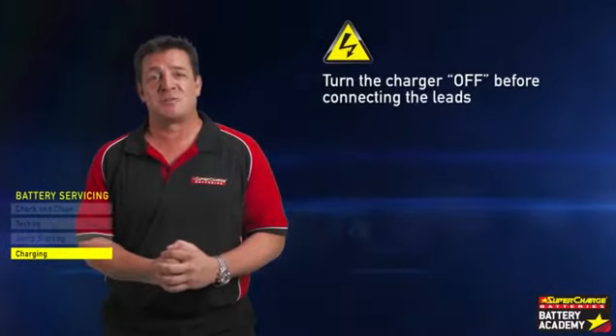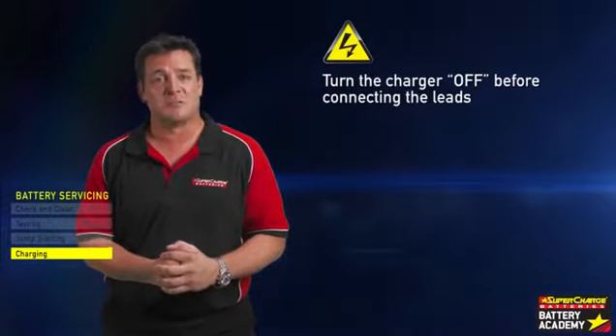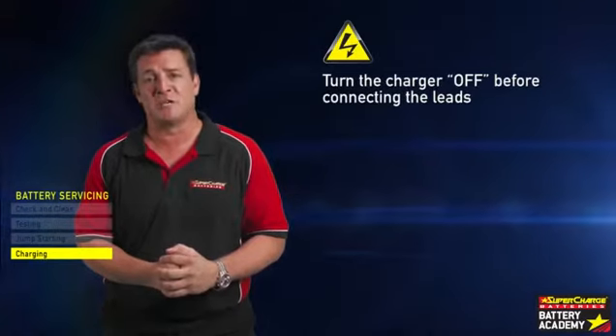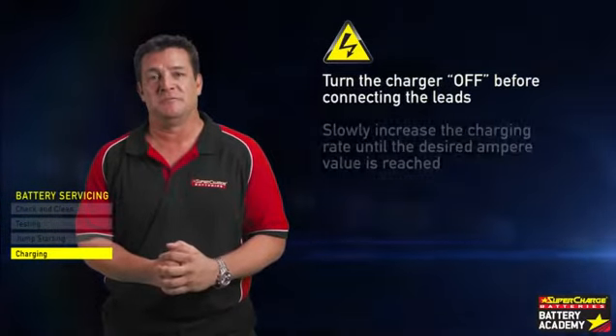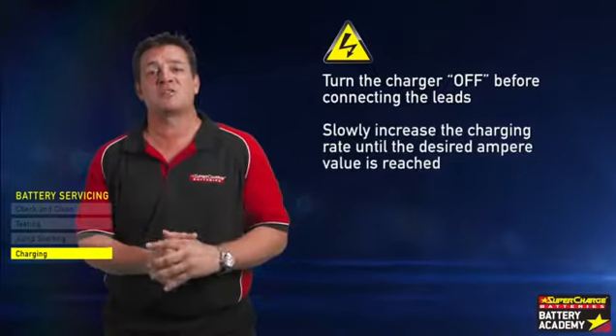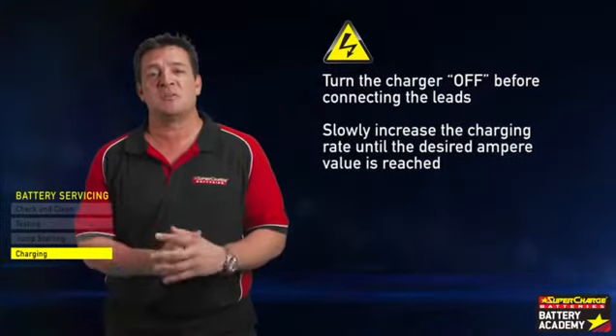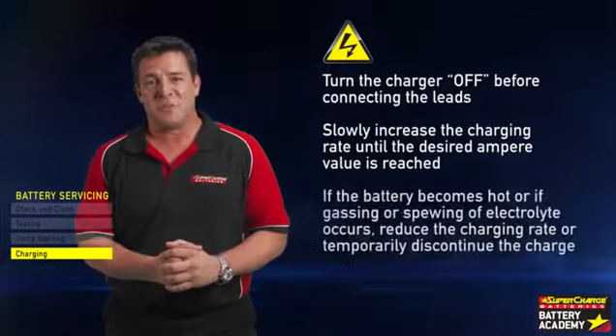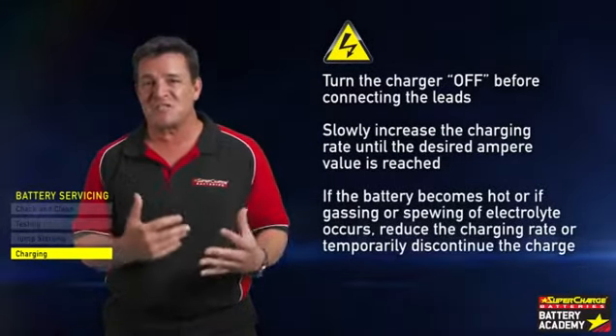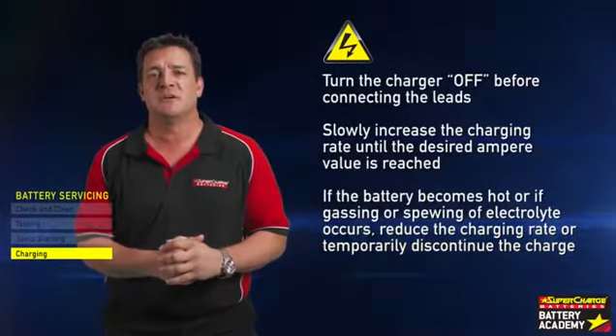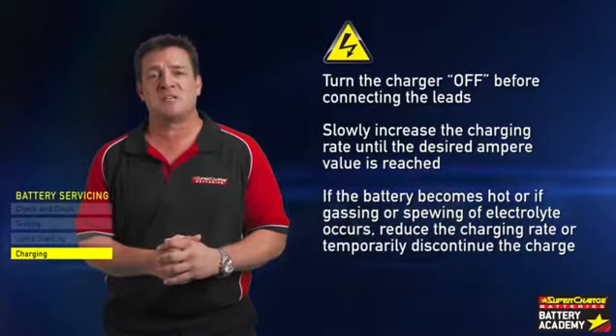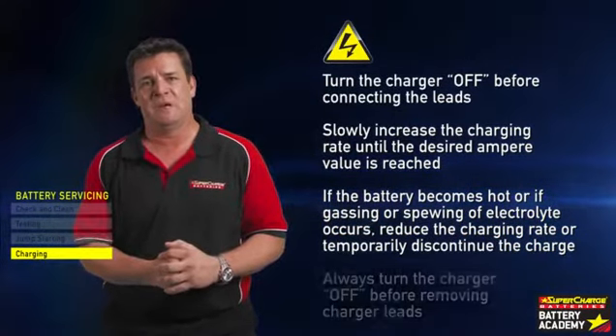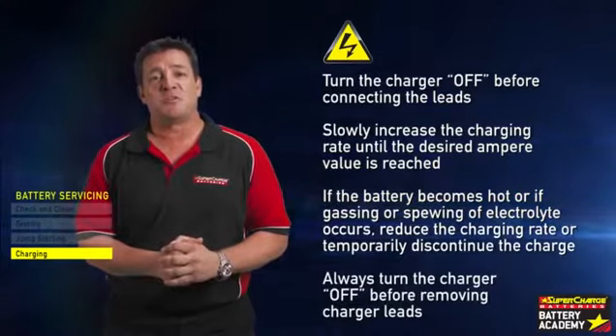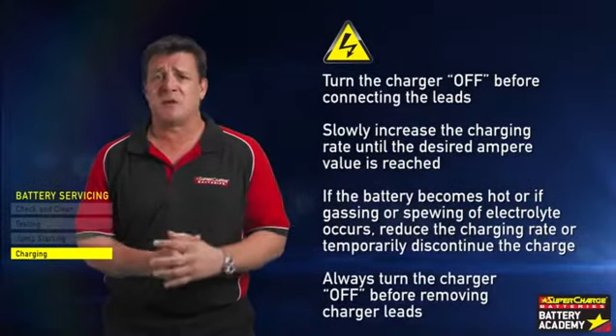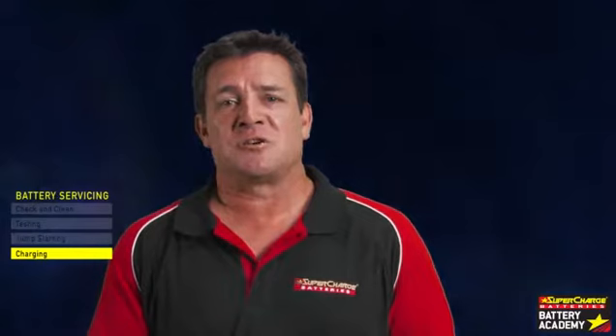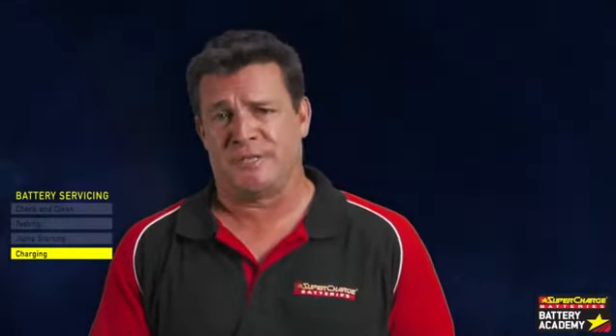Connect the charger leads to the battery, red positive lead to the positive terminal and black negative lead to the negative terminal. Turn the charger on and slowly increase the charging rate until the desired ampere value is reached. If the battery becomes hot, or if gassing or spewing of electrolyte occurs, reduce the charging rate or temporarily discontinue the charge. Always turn the charger off before removing charger leads from the battery to avoid sparks. As the temperature decreases, the electrolyte resists charging.